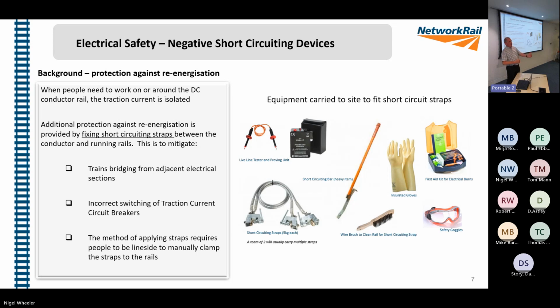There is no chance of that conductor rail becoming live. To do that, we used to have to take all that kit out to site. So we had a tester, to make sure that before we do anything, the conrail is de-energized. We then put a short circuit bar down, because that protects the person actually kneeling down in front of the conductor rail fitting the short circuit strap.